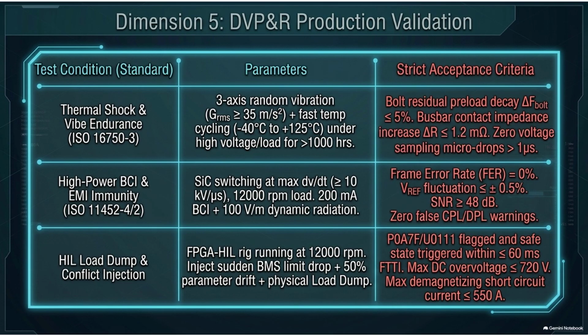Right, so the back electromotive force from those spinning magnets suddenly has nowhere to go. The battery, which acts as the electrical shock absorber for the whole system, is just gone. So the voltage is going to spike instantly. In that exact moment, the physical controller must flawlessly detect the loss of the DC link and execute the stepwise active short circuit. And the FPGA rig monitors the real-time reaction to see if it did it right.